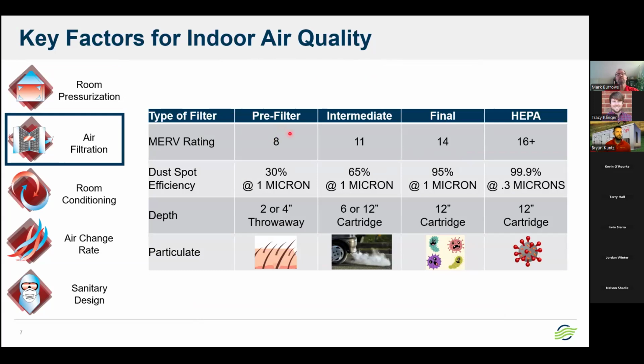Our pre-filters are going to be typically MERV 8, MERV 10 range, and your final filters are going to be MERV 14 onwards, up to your HEPA filters, MERV 16 and up, depending on the application. Rarely, but occasionally, we will see the need for an intermediate filter. Sometimes those pop up during bakery applications where the environment's full of flour. You kind of need an extra catcher's mitt, if you will, to collect the dust in the airstream.